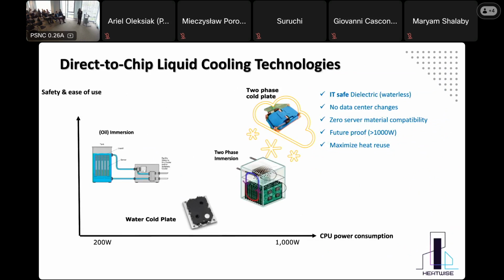The other technology is immersion, where you immerse a complete server in a dielectric liquid - the whole server is immersed inside. The major drawback of immersion is that you need a completely different infrastructure for this purpose. Another thing is that because every part of the server is in touch with the dielectric liquid, it has to be material compatible with this liquid.